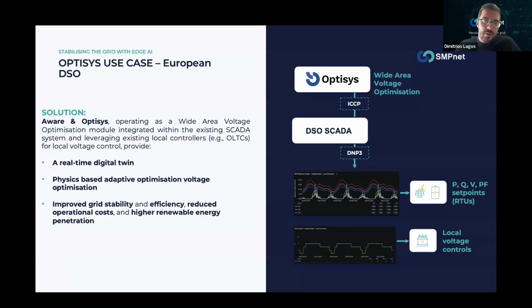This integration goes with the ICCP protocol, where Optisys gets the latest measurements from the SCADA system, performs its calculations, and then sends back the dispatch command to the DSO SCADA that then uses another protocol, in that case DNP3, to control the different DRs in the network.